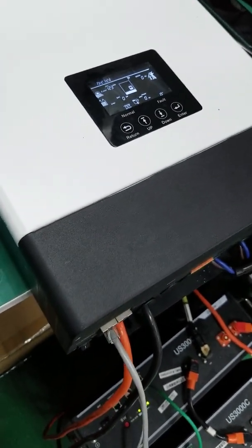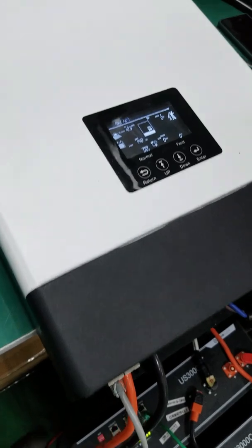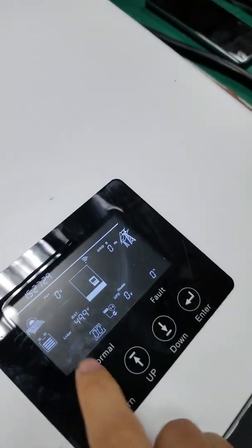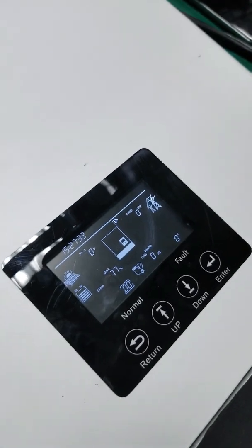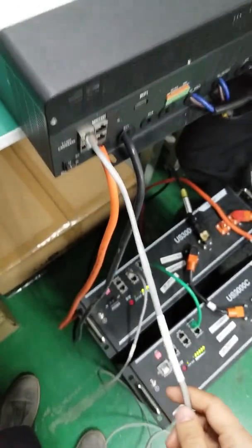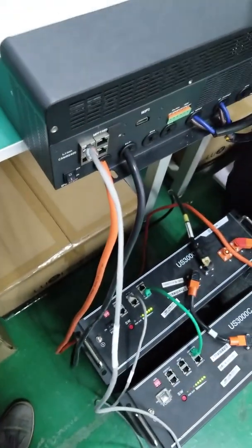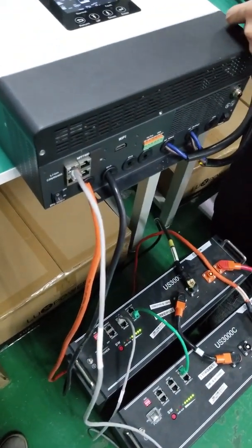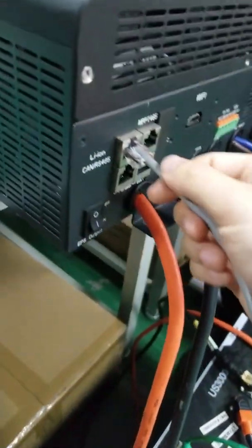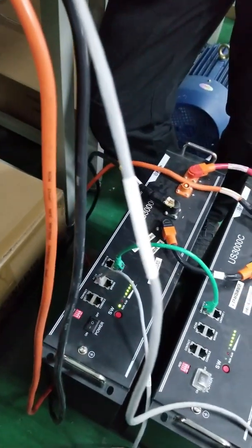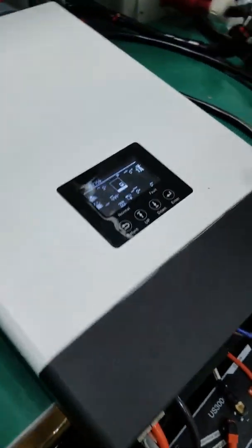We commonly have inquiries from installers coming to us saying they have a problem showing warning code 00. That means communication failure. Then you might need to check your cables. Make sure both ends of the crystal head have the right pin out and it goes to the right port. This is going to the master CAN. Also, the battery is well organized.